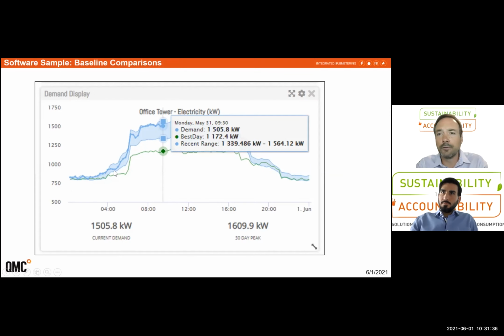And this is an example of utilizing the last 7 days to generate an acceptable threshold for any given load. So the light blue area here is showing what the range has been over the last several days. I believe what we've done in this case is use the last 7 of the same day, so 7 Tuesdays as an example, and you want to see that your consumption is within there. You'd also see a best day that you could be targeting towards. This can be at a building level, at a piece of equipment, or for an entire floor, and you can take actions to actually get towards your energy objectives using this data.